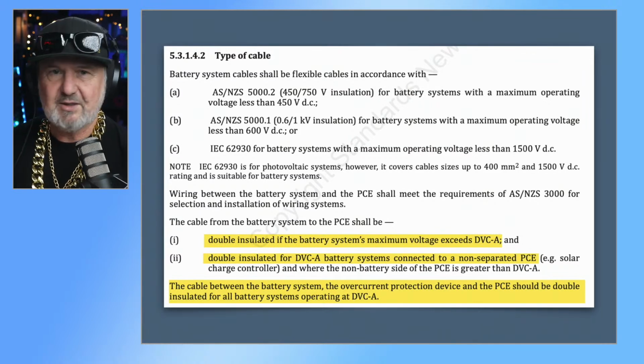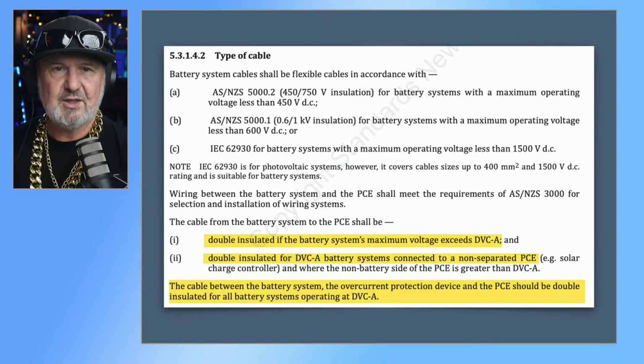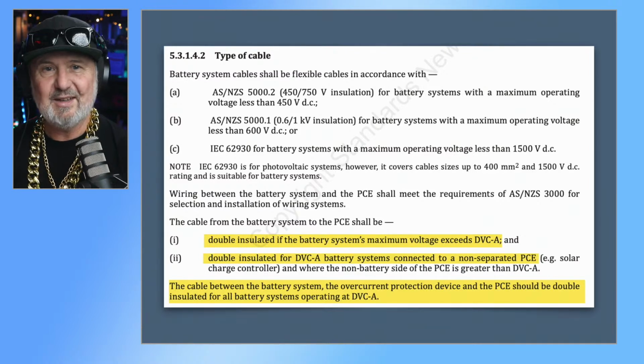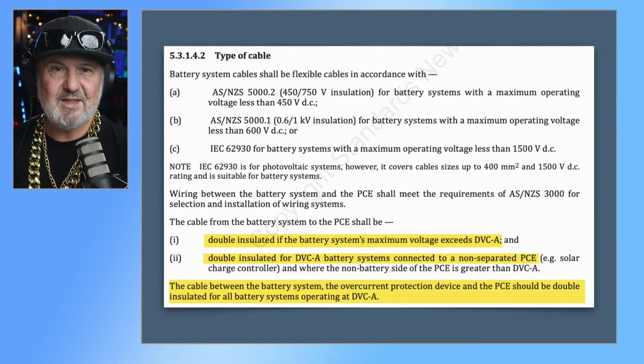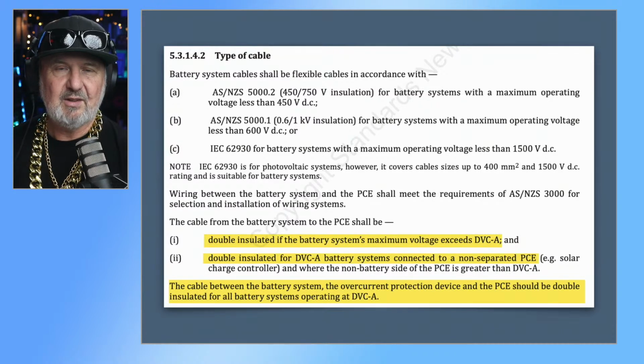So, yeah, coming back to DVCs, decisive voltage classifications are a move away from our more conventional AS/NZS 3000 wording of LV and ELV. So in AS/NZS 3000, we refer to extra low voltage as below 120 volts DC, and low voltage is over 120 volts DC. We'll ignore the AC side because we're talking about batteries here.